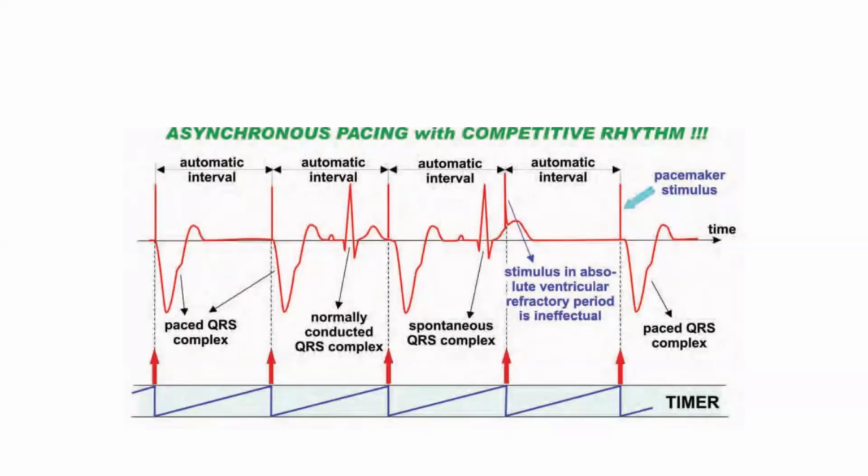The pacemaker didn't do anything except what you programmed it for. You just give him the order of continuous pacing at fixed rate every 1000 milliseconds. So it's fine. But because it doesn't see and it can't evaluate the myocardial depolarization and the QRS complex, because this function is inhibited, it doesn't see, and this may cause the impulse to become in the refractory period, and this we call functional non-capture.